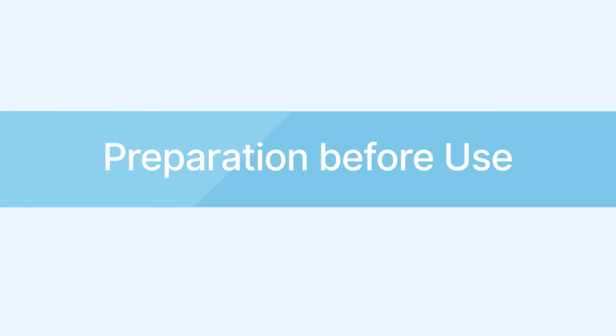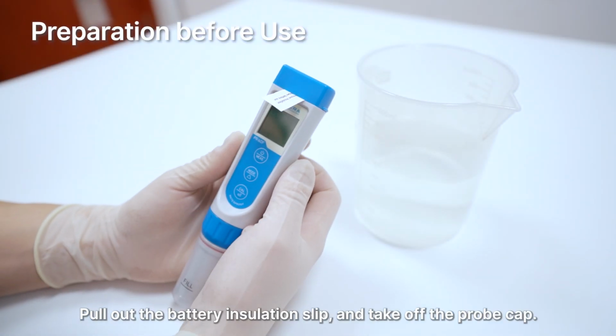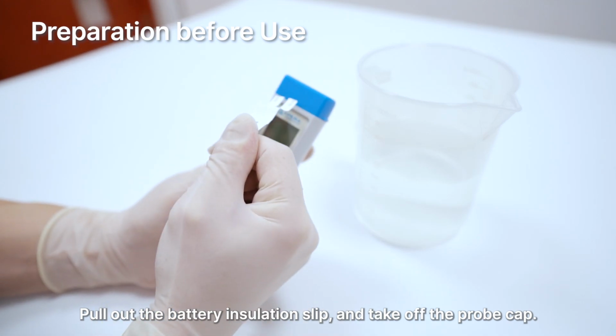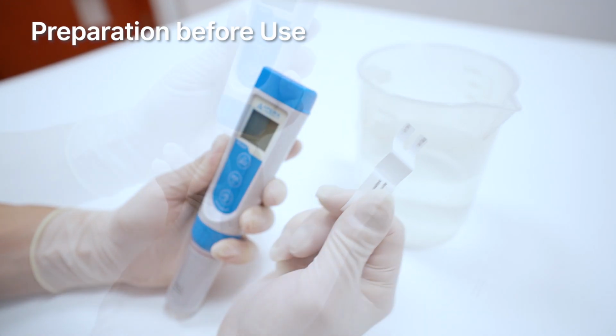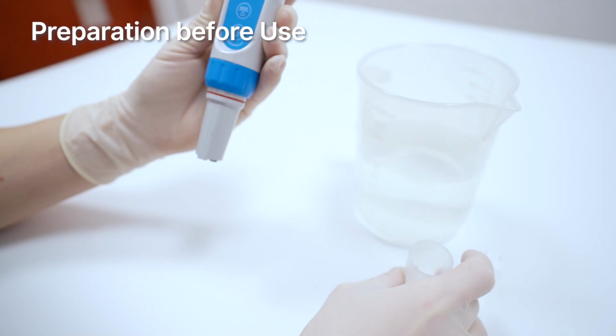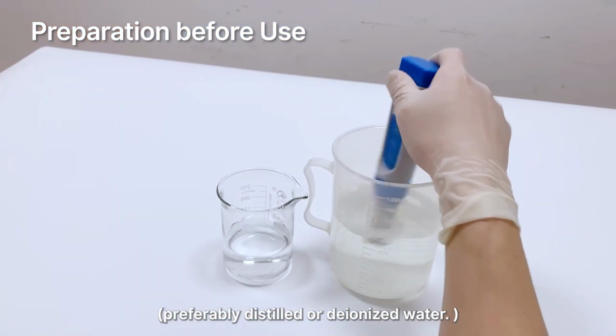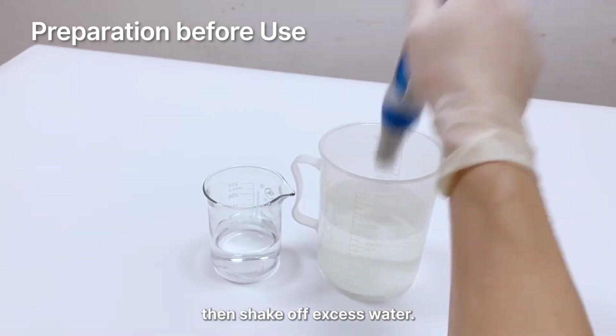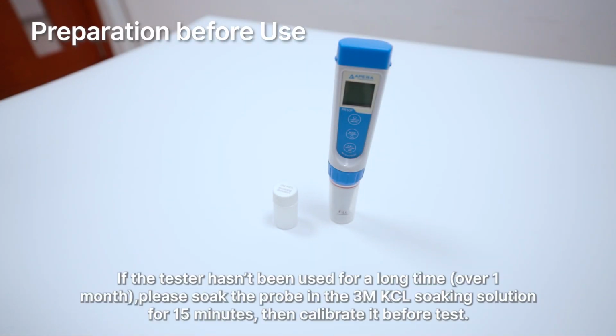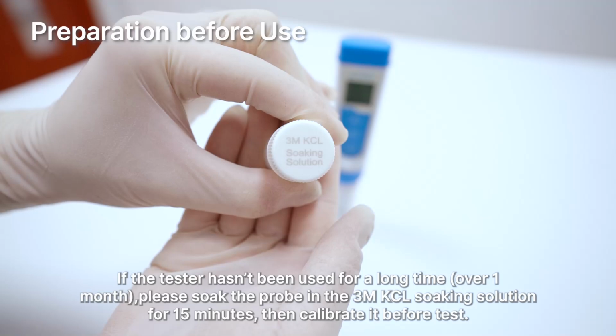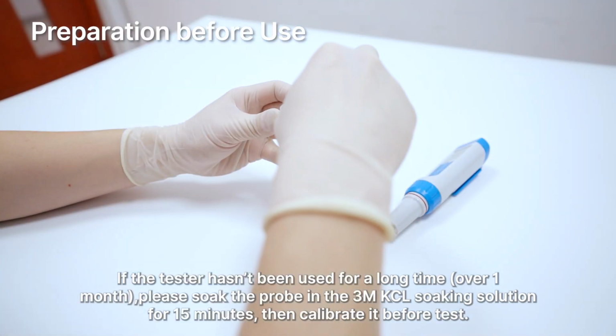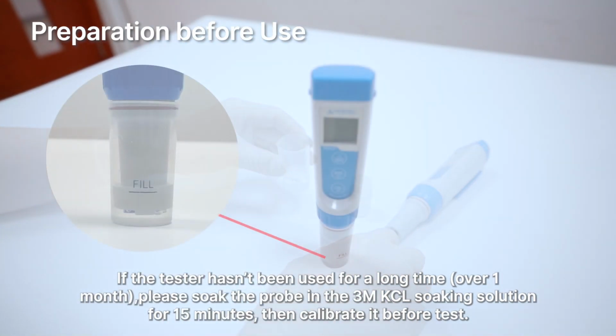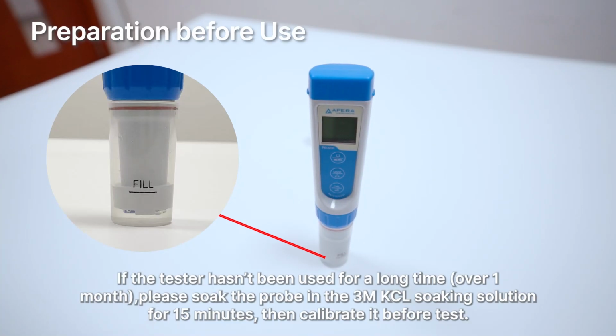Preparation before use. Pull out the battery insulation slip and take off the probe cap. Rinse off the probe in pure water, preferably distilled or deionized water, then shake off excess water. If the tester hasn't been used for a long time, please soak the probe in the 3M KCl soaking solution for 15 minutes, then calibrate it before test.